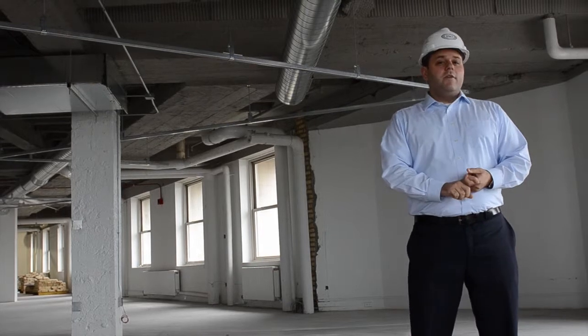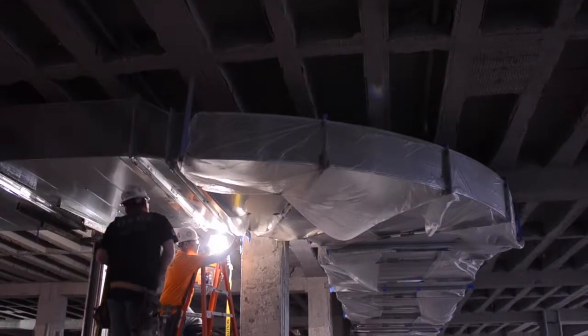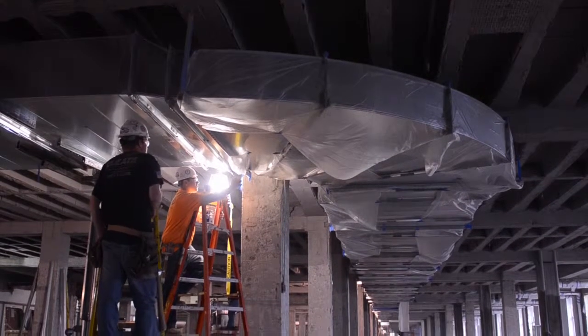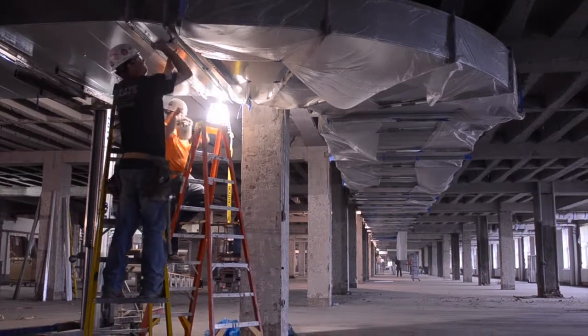For the lab MEP systems, instead of using typical overhead systems, we're using a chilled beam system. This requires only the amount of outside air necessary to ventilate the space to move through the ductwork, while cooling is accomplished by chilled water. It's a lot more efficient, saves fan energy, and you get a lot more cooling for a smaller ceiling sandwich.